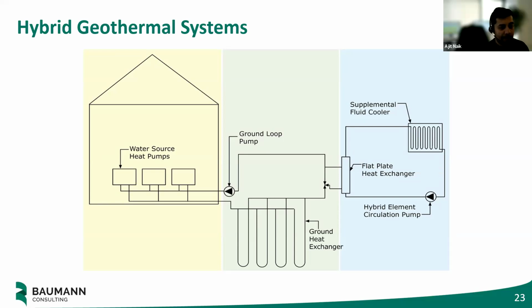If it's really heating dominated, you go deeper so you can tap into that earth warmth. If it's cooling dominated, you go a little bit shallower so you can take advantage of the cooling effect you get in the wintertime from the air. Either way, when you're constrained by space and can't quite meet your load, these hybrid systems are a great option for cashing in on a lot of the benefit.